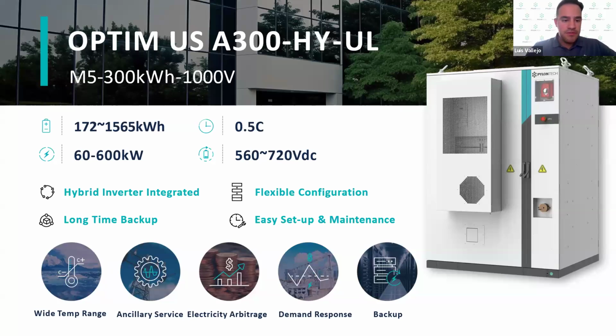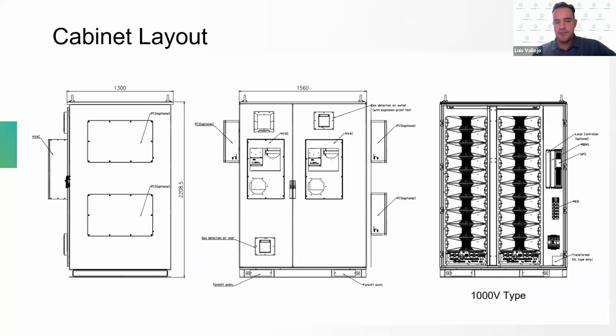All right, so this is our Optim US M5. This one obviously uses our M5 module, and the capacity ranges from 172 kilowatt hours to 1.5 megawatt hours. It can be paired with inverters ranging from 60 kilowatts all the way to 600 kilowatts. This one is half C and is DC certified UL 9540. These types of systems are mainly used for electricity arbitrage, demand response, and backup power. And here's the cabinet layout, where, as you will be able to see, the PCS can be placed in 3 different locations depending on the site or the configuration that you want. And you can either have 1 string or 2 strings inside the cabinet.